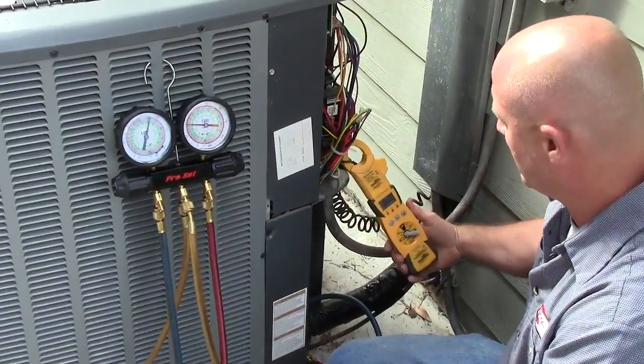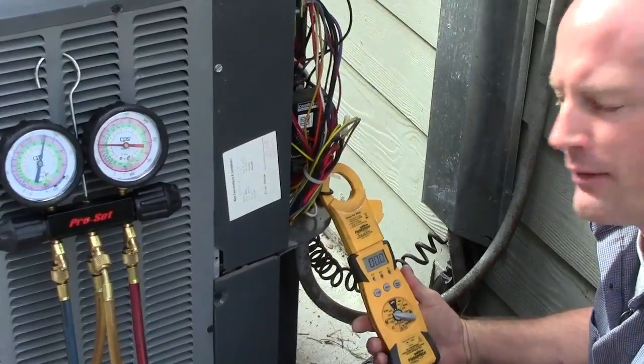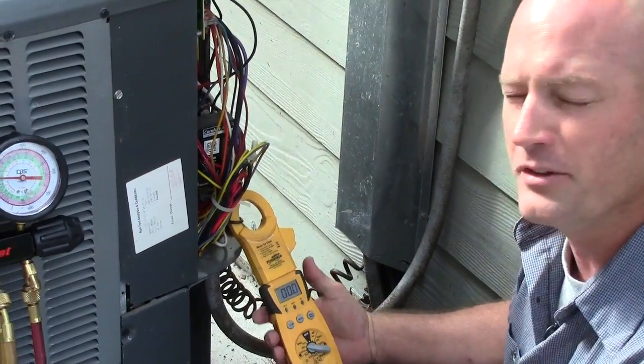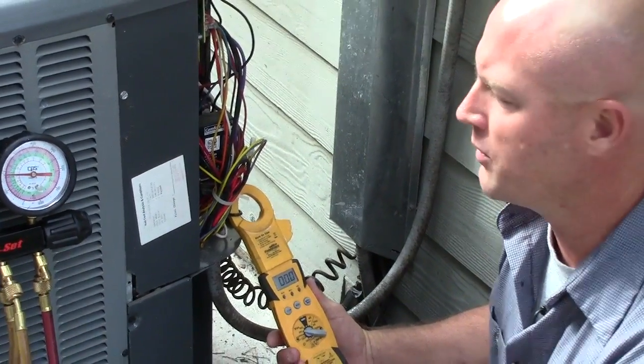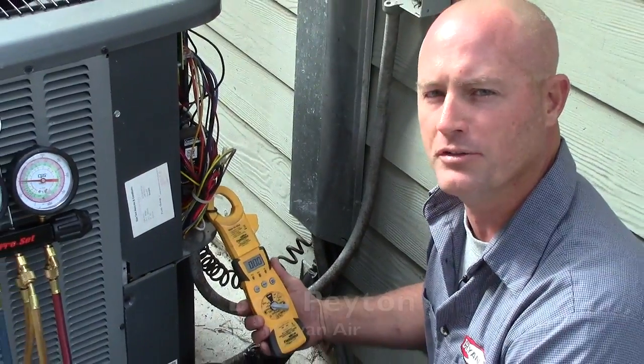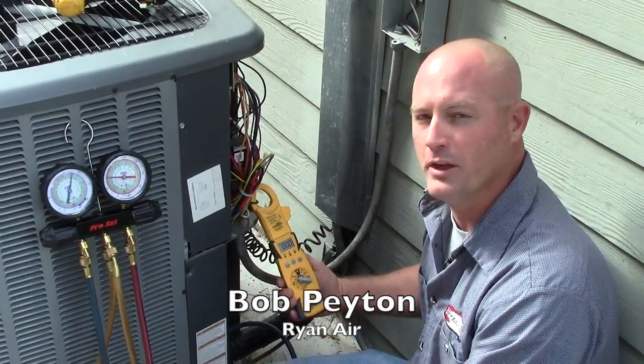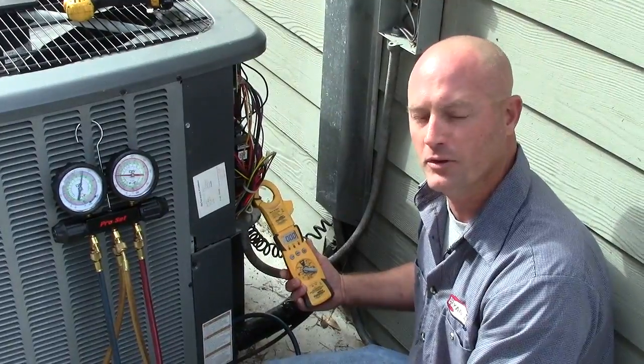Hanging here outside the unit is an amp probe. It is clipped to your high voltage wire. We use this device to make sure that the motors, when they're running, have proper amp draws. Make sure they're working within the parameters in which the factory prefers them to work.